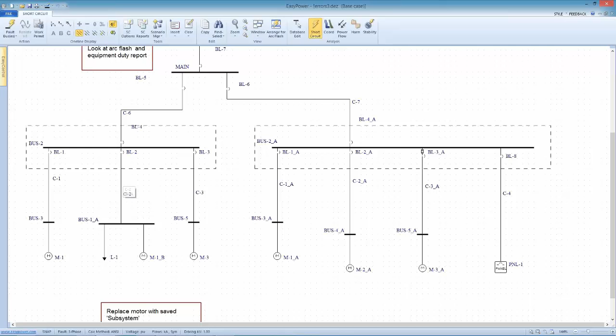Finally, when I go to change from database edit focus to short circuit focus, if there is a mistake, for instance, if I haven't adequately characterized the cable inputs, the cable contents for this particular cable, it will alert me to that fact and not allow me to change focus from database editor to short circuit. And this can be done for the whole system, frankly, or just a portion of the system that I'm working on. So it'll give me a report or show, highlighted in red, the mistakes I'm making here. So those are pretty much the utilities that are built into EasyPower.